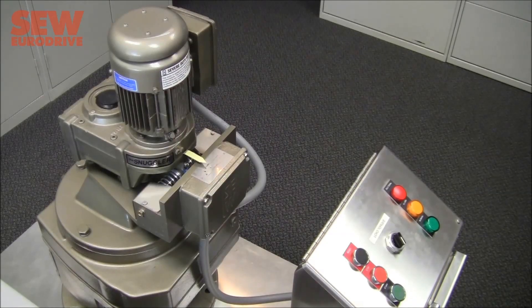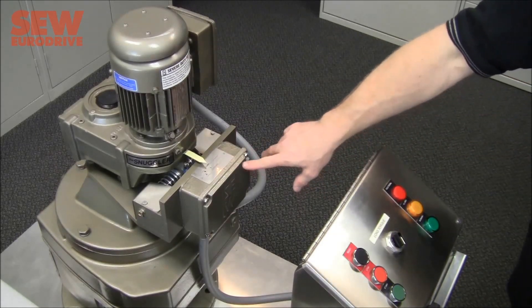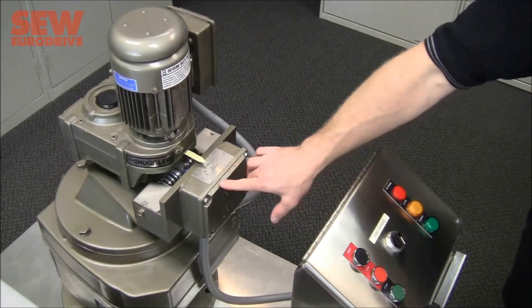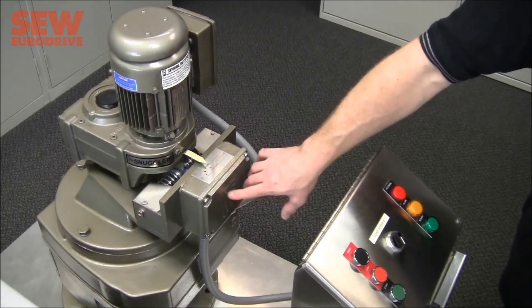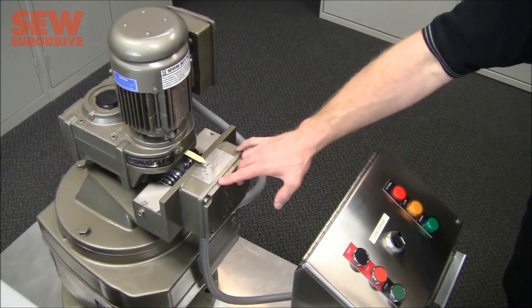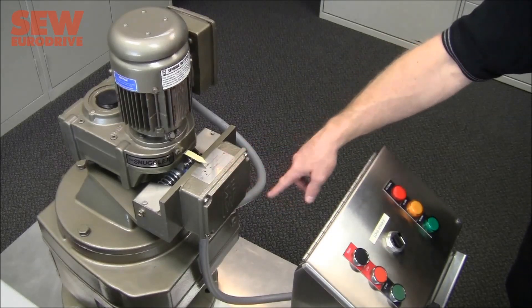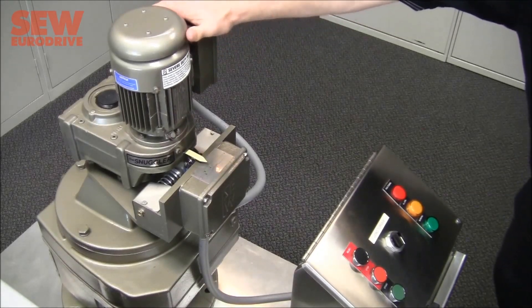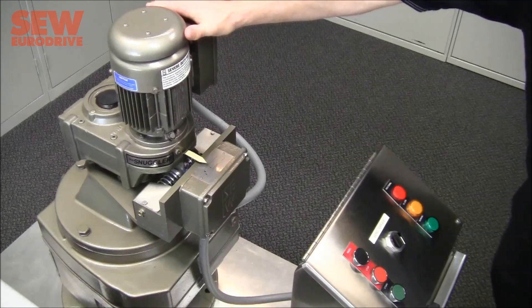The TS units are built very robustly to withstand the environmental conditions they'll be exposed to. The hermetically sealed sensors are placed into an IP66-rated cast iron conduit box. You can run hardwired connections for power and sensors in the lower conduit box, but make sure to use a flexible connection for powering your electric motor, because if it's not allowed to pivot freely, it will interfere with the normal operation of the TS unit.